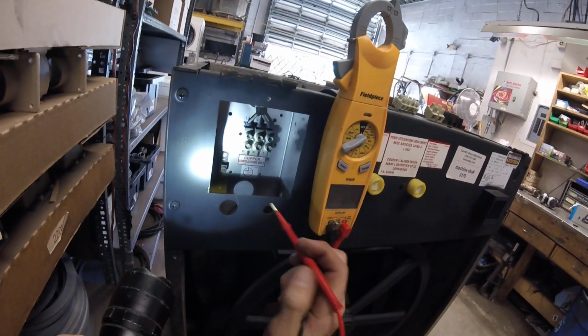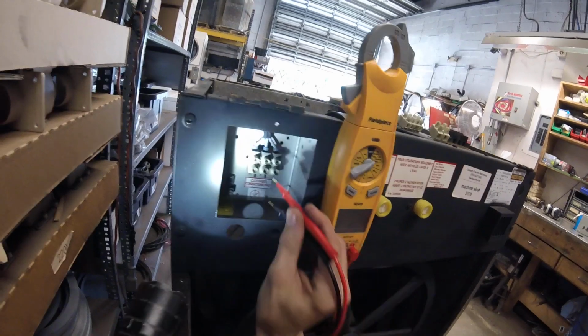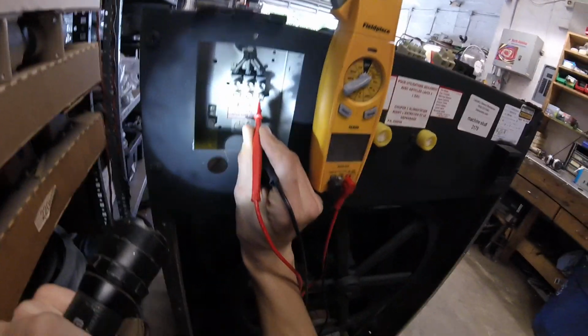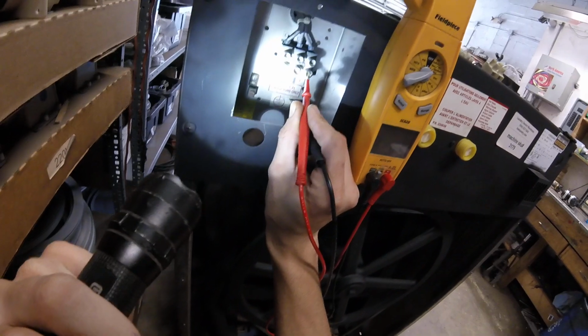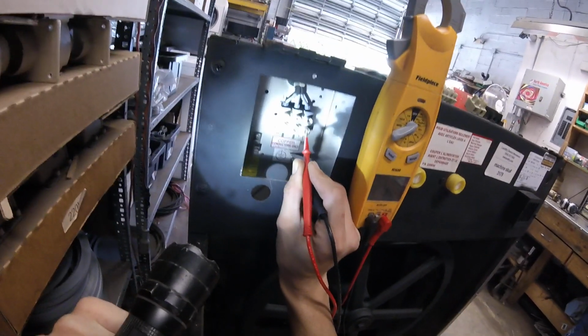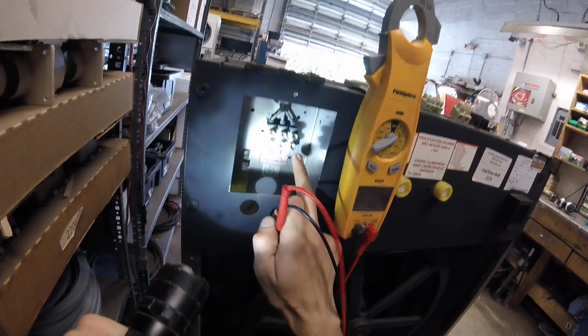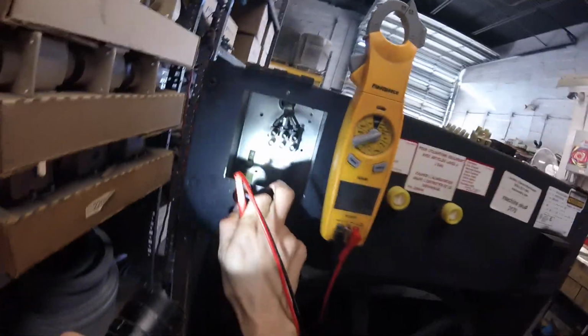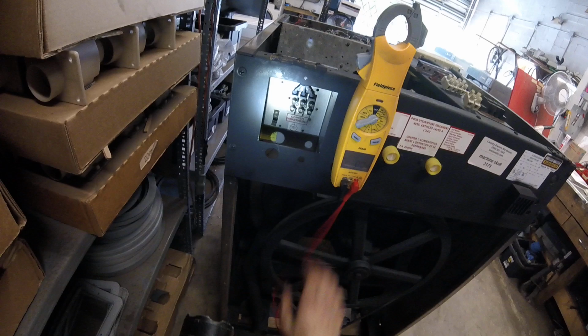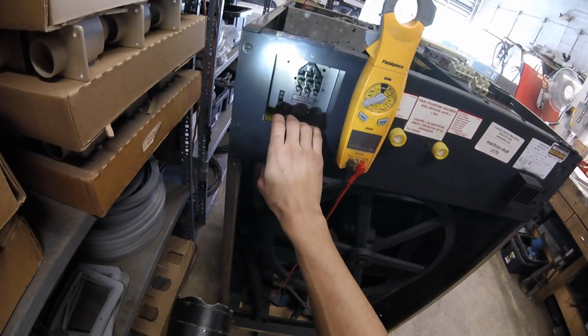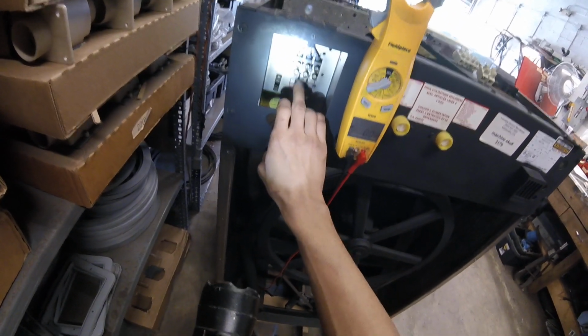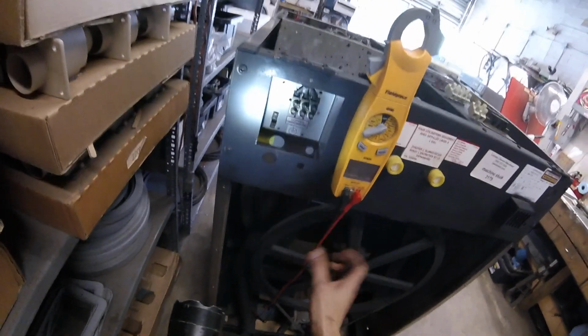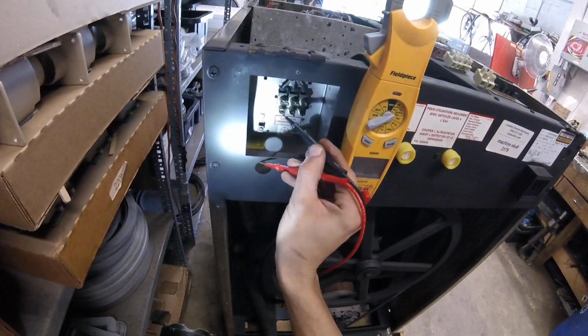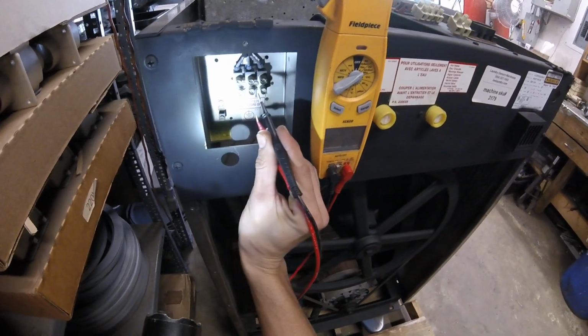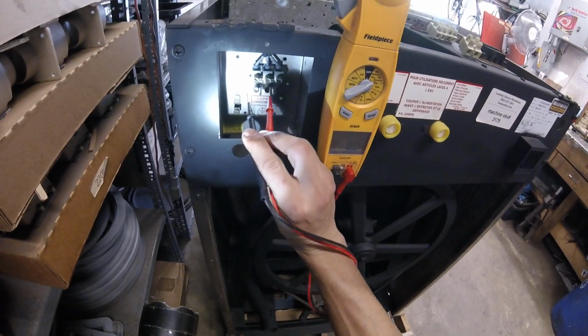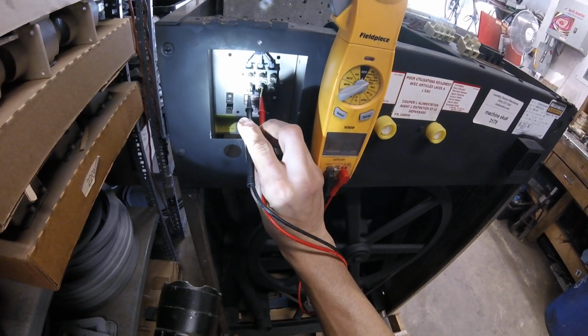If you have one leg that by itself you're reading 220 when you jump it to ground, you might be running a phase generator instead of getting your third phase from the power company. In that case, just make sure that your 220 leg is on L3, not on L1 or L2. Now for a single phase machine, you're just going to have L1 and L2 and ground. So you would have L1 here, L2 here. They should both be reading 110 to 120 volts when you go from L1 to ground and L2 to ground. And again, you should be getting 220 volts when you jump across.